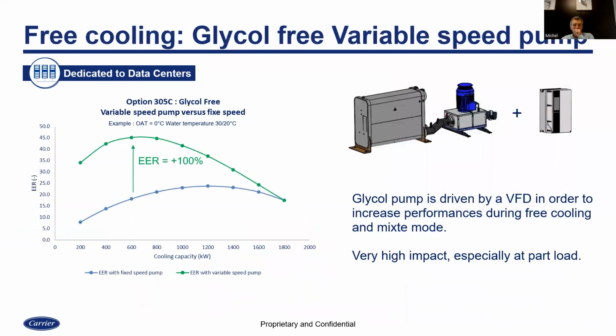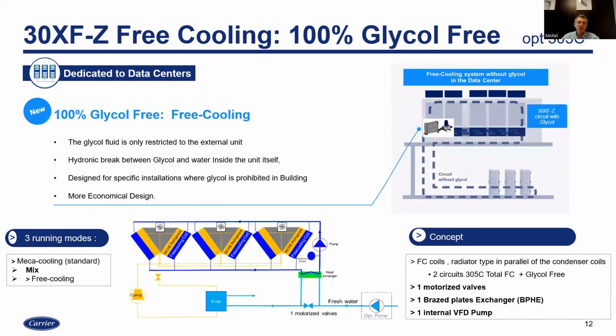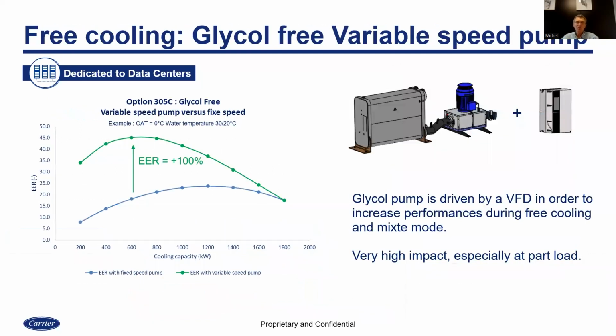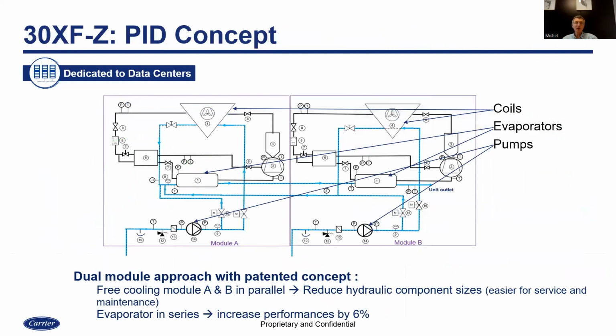And in this particular option, the question of what the speed of this pump should be versus flow and load is a question of optimization. So we have made this pump variable speed, and we have realized that by smart optimization of the speed of this pump, we can benefit from much higher efficiency than in the traditional one. But this is just an element of our optimization. So this is actually what you call the PID of the system. So you can see it's a little bit complicated.